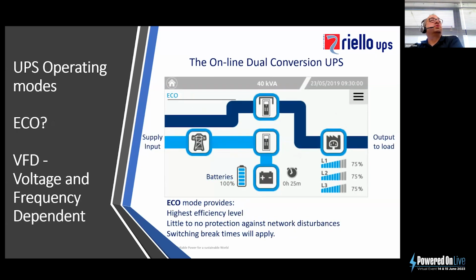Another mode of operation for the online dual conversion UPS system is the eco mode. The eco mode is exactly the same UPS. They can all do these features. The eco mode operates whereby the load is now being powered through the bypass line. So this time the UPS system is not performing the dual conversion process, albeit we are still maintaining the batteries so that in the event that there is a mains failure, the battery system will be available should it need to be.